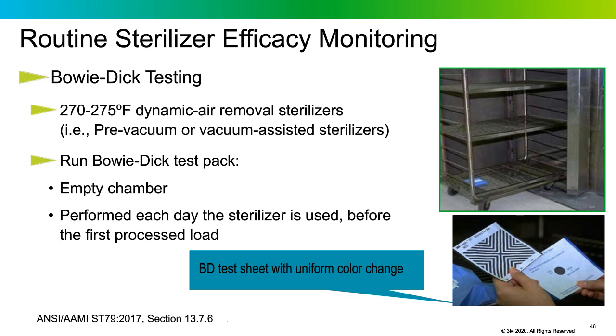ST-79 also requires a special daily test to verify that a sterilizer's vacuum system is working well. For dynamic air removal steam sterilizers, routine efficacy testing includes the daily Bowie-Dick test, performed in an empty chamber before the first process load. A nice uniform test sheet indicates that air removal was adequate and steam penetration was sufficient.